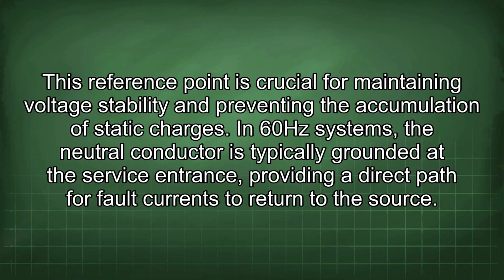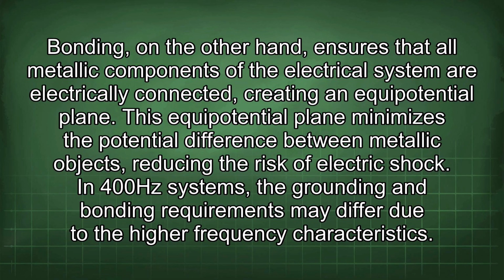In 60Hz systems, the neutral conductor is typically grounded at the service entrance, providing a direct path for fault currents to return to the source. Bonding, on the other hand, ensures that all metallic components of the electrical system are electrically connected, creating an equipotential plane. This equipotential plane minimizes the potential difference between metallic objects, reducing the risk of electric shock.